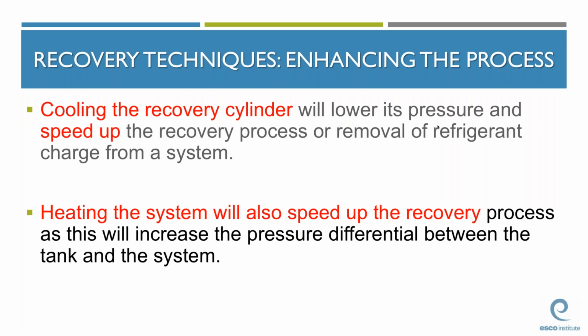This next slide basically talks about high pressure going to low pressure. If we increase the pressure differential, we're going to increase the rate of flow from high pressure to low pressure. So the refrigerant recovery process can be sped up by increasing the pressure difference between the system and the recovery tank. And this can be accomplished in 2 ways. First, the recovery cylinder can be cooled to lower its pressure. Second, heat can be added to the system to increase the pressure in the system. Either method can be used to increase the pressure difference between the system and the recovery cylinder.